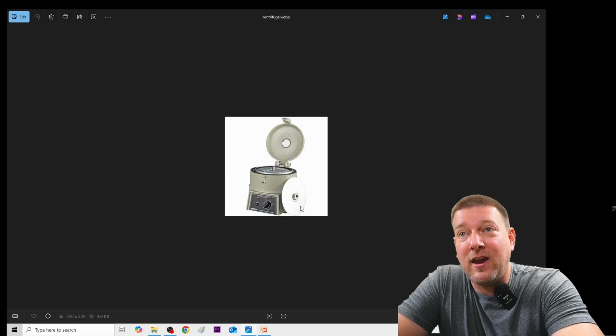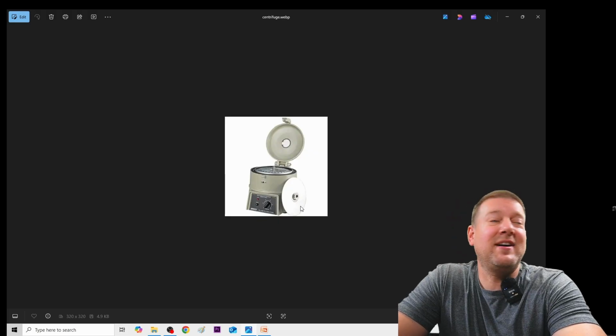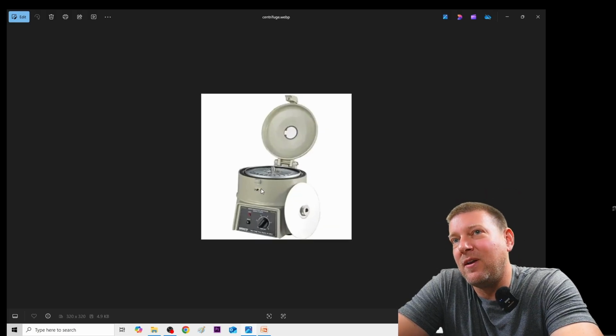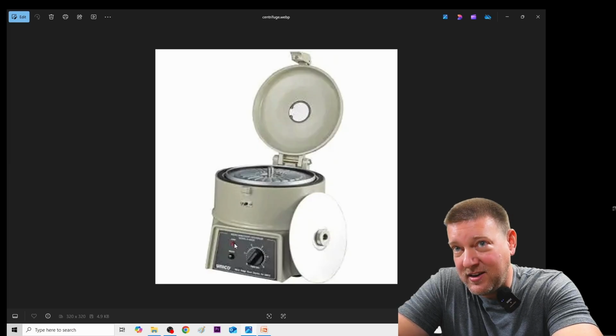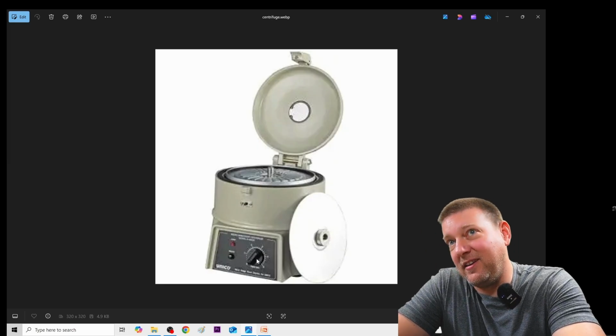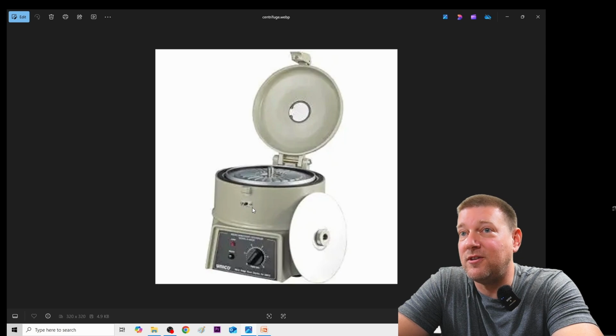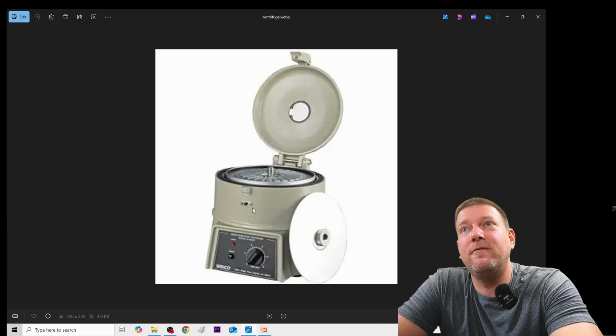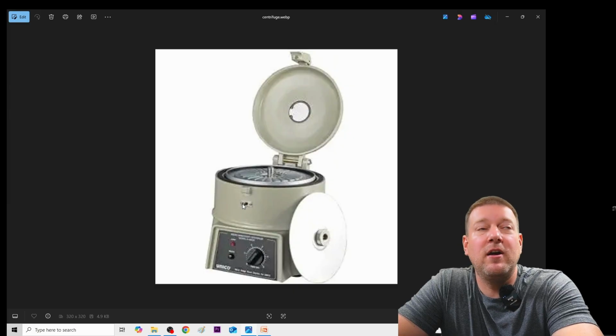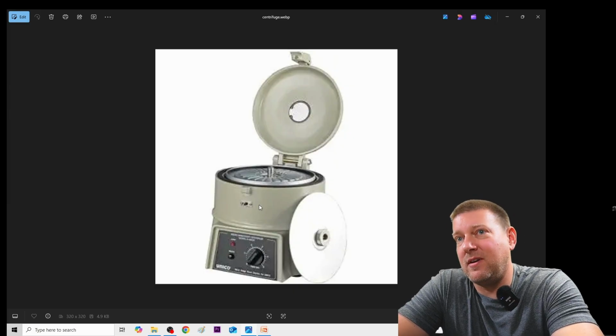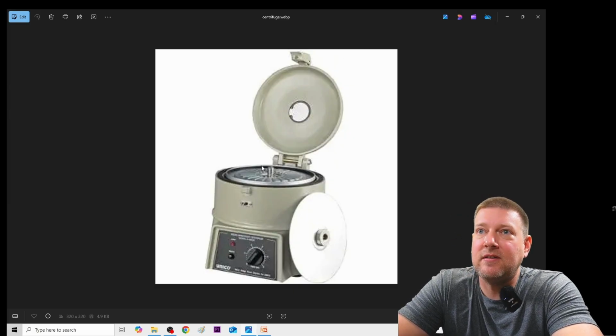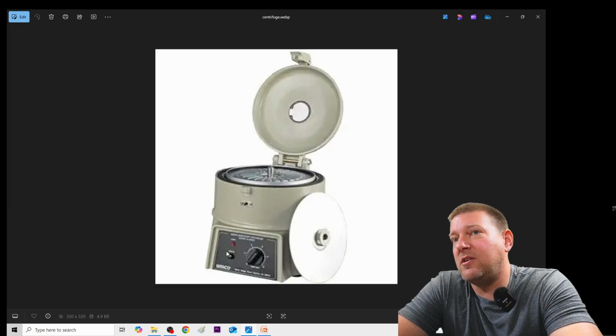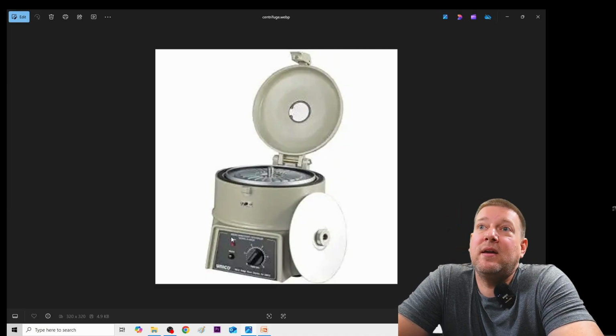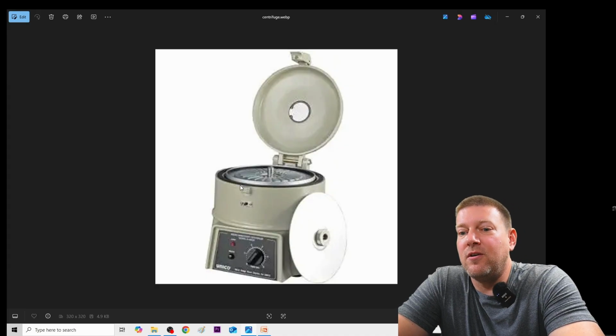And we have an old centrifuge. Take a look at it. We have neon indicators, an analog timer, and notice there's no adjustable speed. Gen 1 product for sure. And there's almost definitely an interlock right here, which is going to be your lid detect. So if your lid doesn't come down, there's no AC power to the control, and there it is. That's the old way of protecting you.